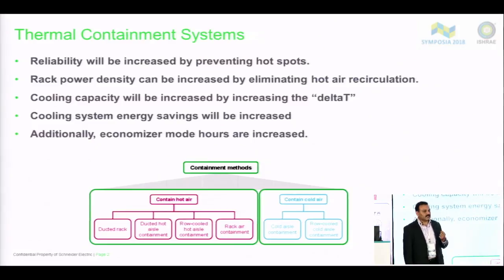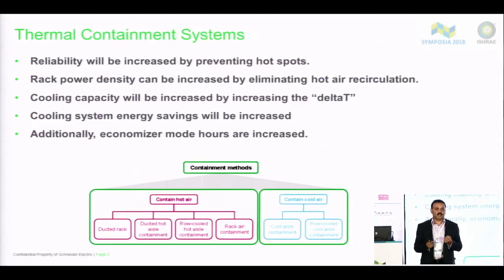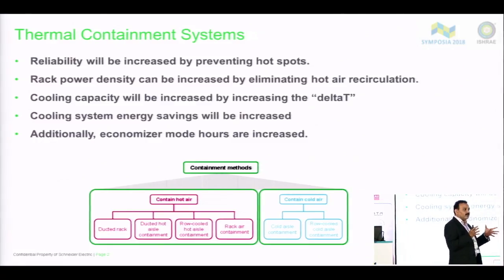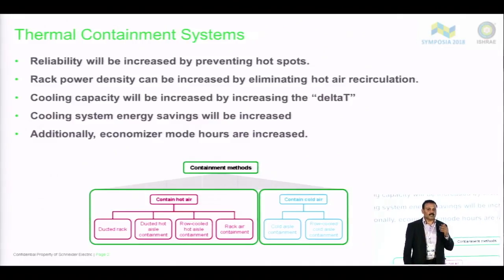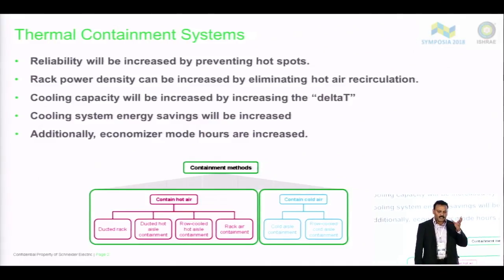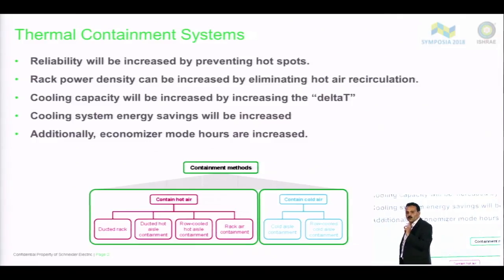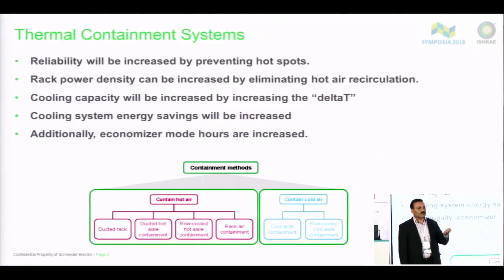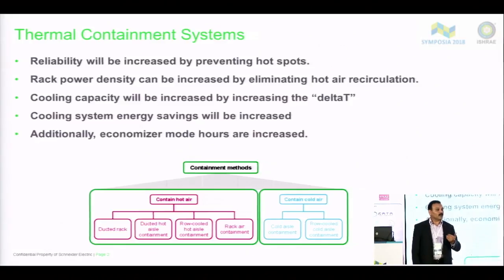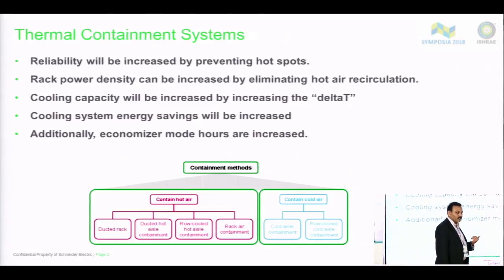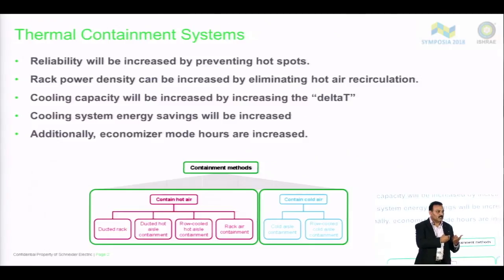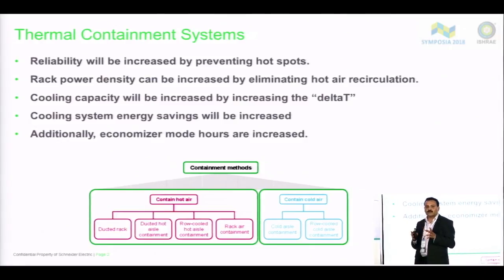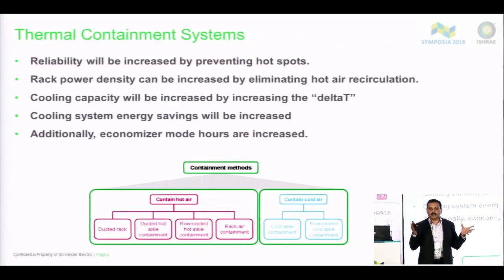Containment solutions increase the delta T, that is the difference between the cold supply air temperature and the hot return air temperature that a cooling unit gets. In an uncontained, very conventional data center with a raised floor, it is estimated that more than 50% of the cold air goes back to the cooling unit itself. It bypasses the entire system, through leakages and other means, which compromises the efficiency of the entire cooling in the data center floor.